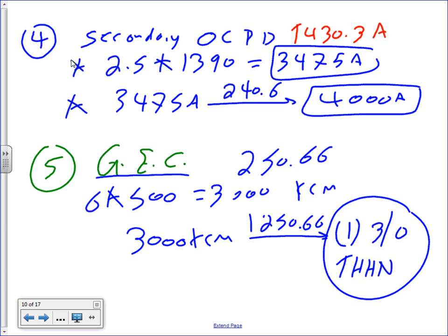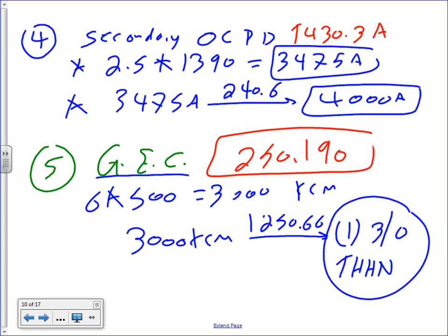Okay, 250.190. Can you guys put the reference here? Actually, your reference here is 250.190. That's the high voltage reference, 250.190. Which actually refers you to table 250.66 anyway, but just a reference. Okay, let me move into one very important thing, guys, and then I promise I'll let you go. Any comments, any question about this? See how easy and nice and easy breezy?